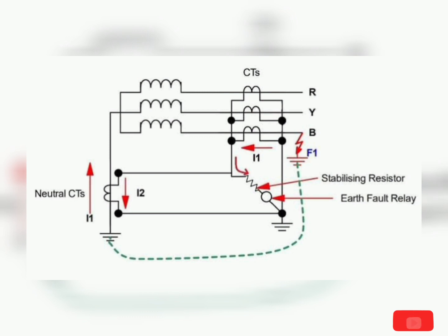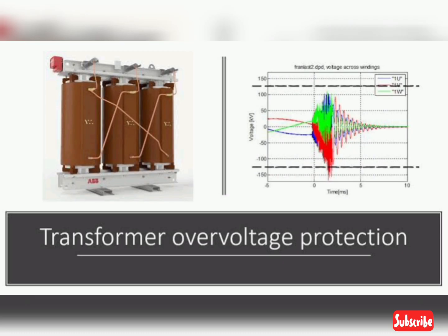Earth fault protection detects earth faults in the transformer winding and trips the circuit breaker to isolate the faulty transformer. Voltage protection monitors the voltage level of the transformer; if the voltage exceeds a certain limit, the circuit breaker will trip to protect the transformer from damage.